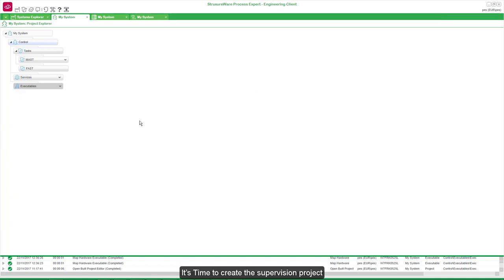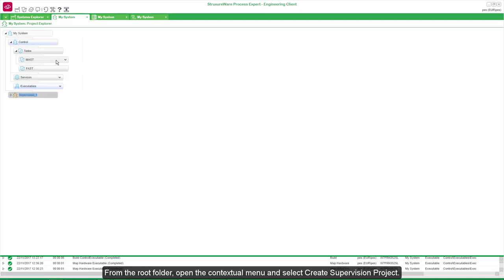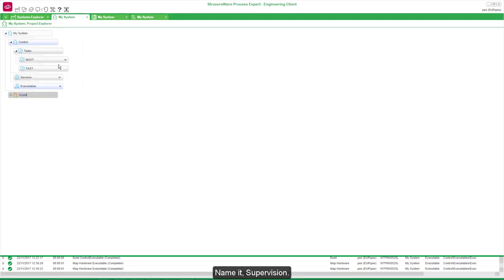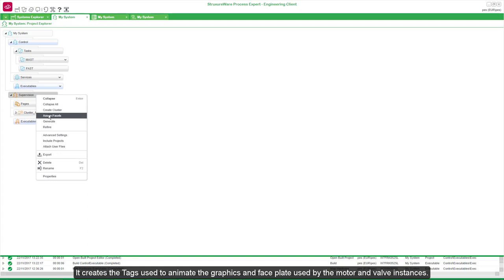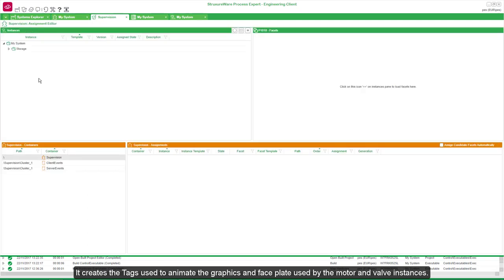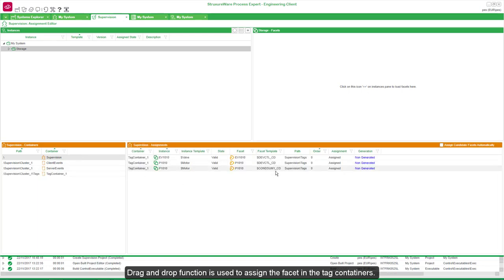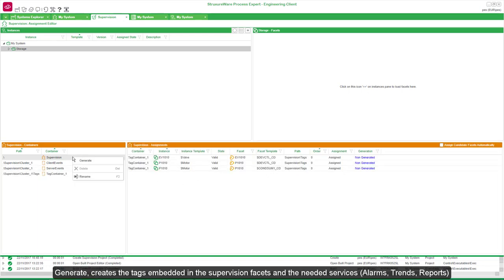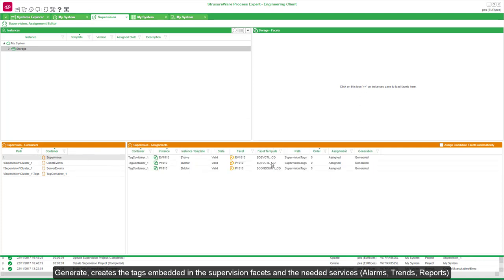It is time to create the supervision project. From the root folder, open the context menu and select Create Supervision Project. Name it Supervision. We assign the supervision facets, which creates the tags used to animate the graphics and faceplates used by the motor and valve instances. Drag and drop is used to assign the facets in the tag containers. Generate creates the tags embedded in the supervision facets and the needed services: alarms, trends, and reports. Close the editor.